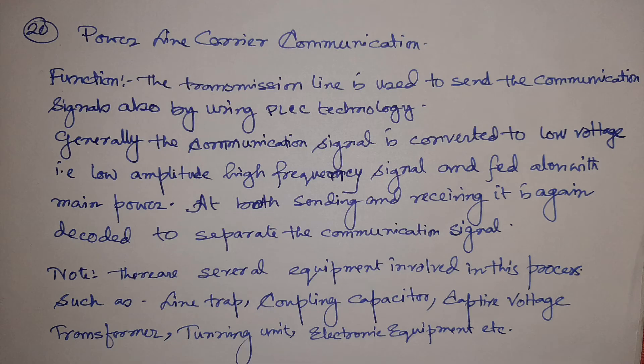Our next item is power line carrier communication, or PLCC. This is a very interesting concept: the transmission line is not only used for transferring power but also used as a communication line. Both the power signal and the communication signal are sent through the transmission line. The communication signal is converted into a low amplitude, high frequency signal and fed along with the main power. At both the sending end and receiving end it is decoded and the communication signal is separated.